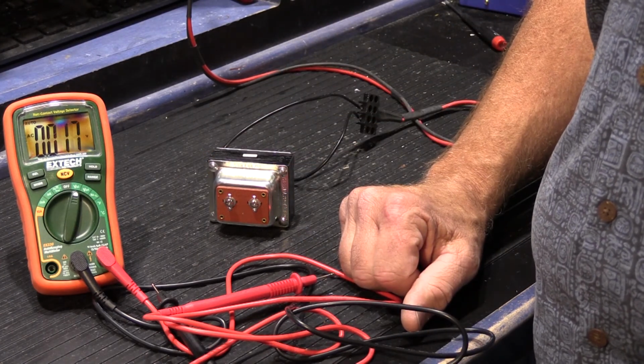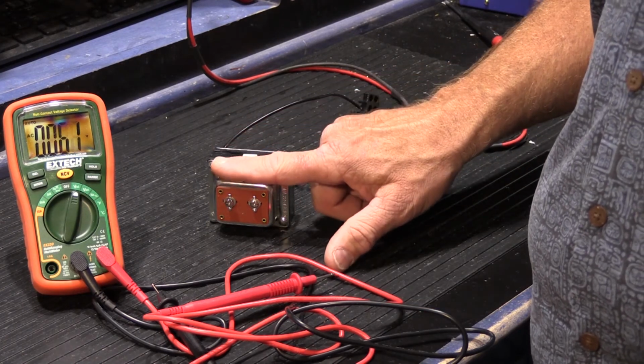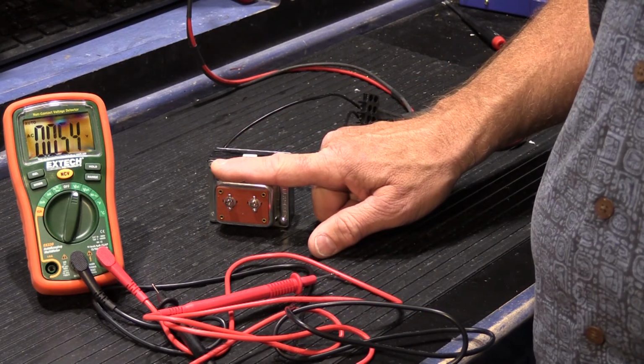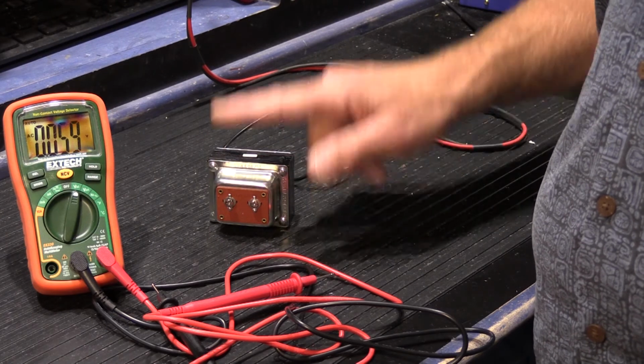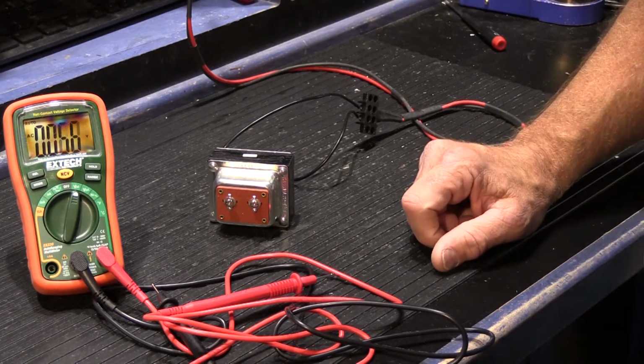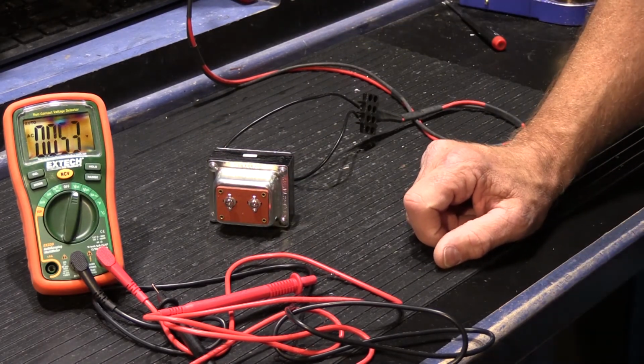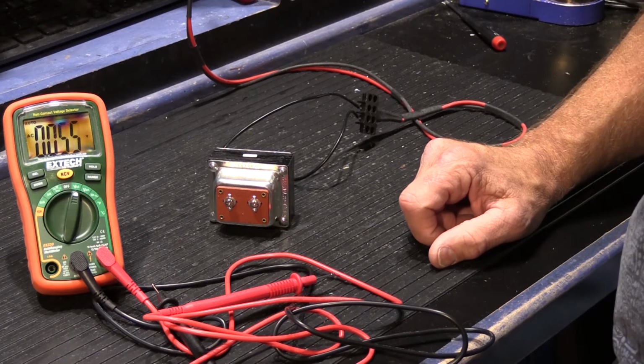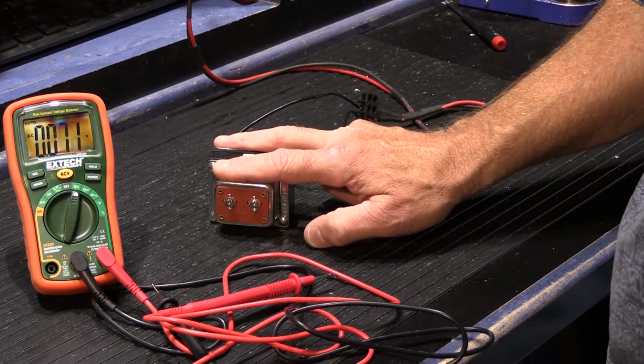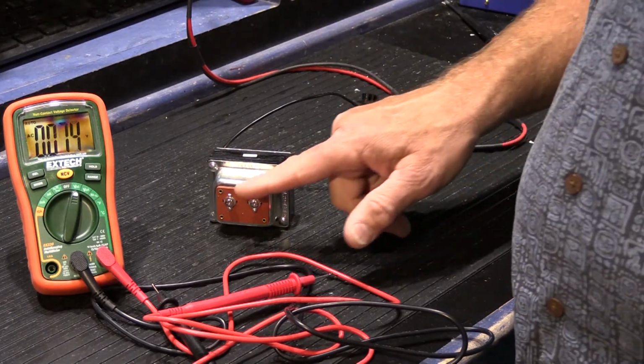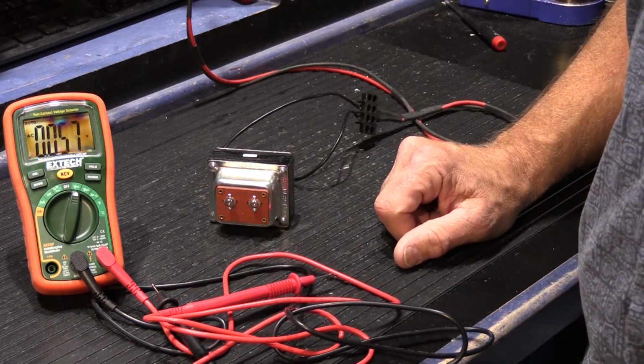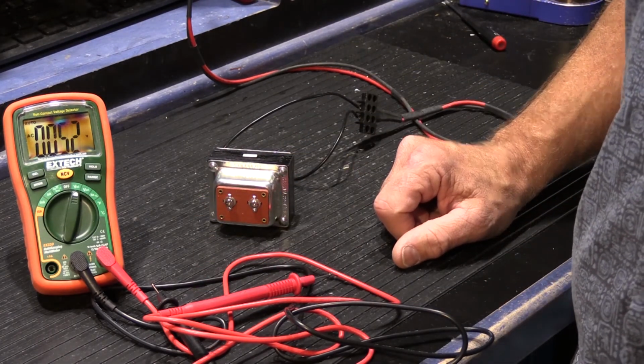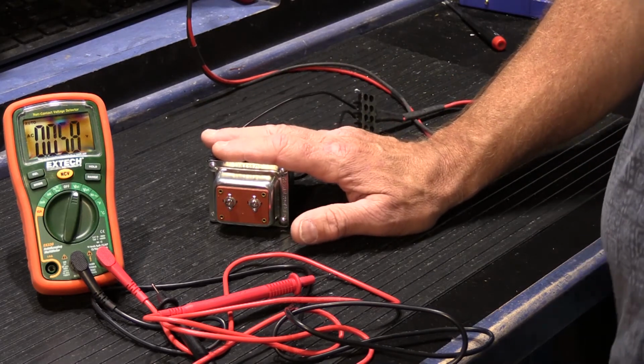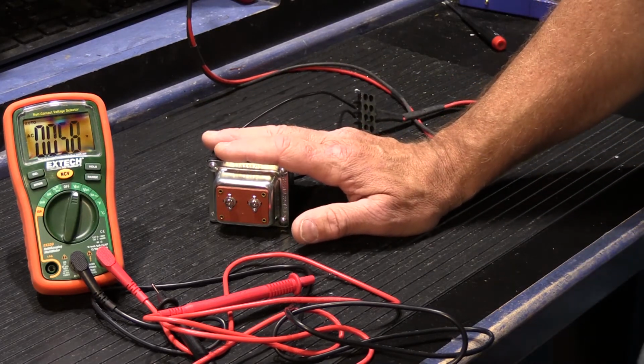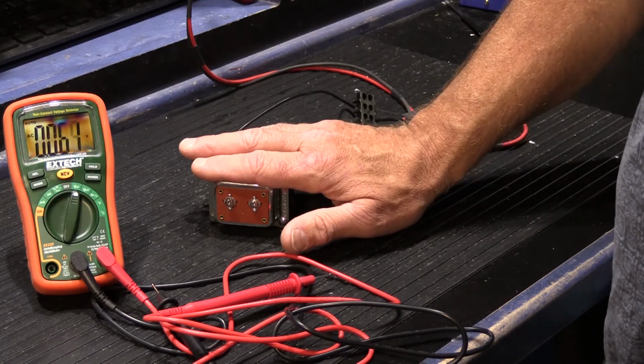The last condition is you put your finger on the metal part of the transformer, count 3, 2, 1, and oh my God it's hot, you've got to take your finger off. That's burning hot, and that's bad — not normal. If your transformer is burning hot, most likely your intercom master station has some kind of fairly serious problem that's overloading the transformer. To prove that to yourself, because people don't always believe what I tell them, here's what you do.